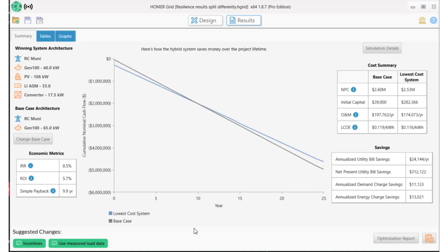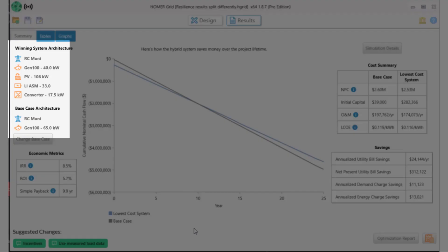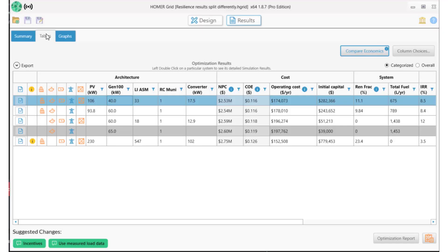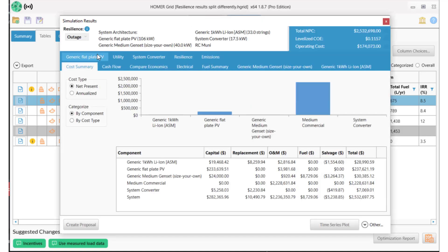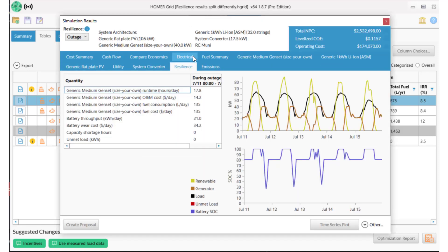And this is a better result. The net present cost and the levelized cost of energy are lower than for the other system, and the winning system now includes storage and a much smaller generator. If we look at the details of the outages, we now have a smaller generator that's operating only 18 hours a day — not 24 — and the battery is assisting.